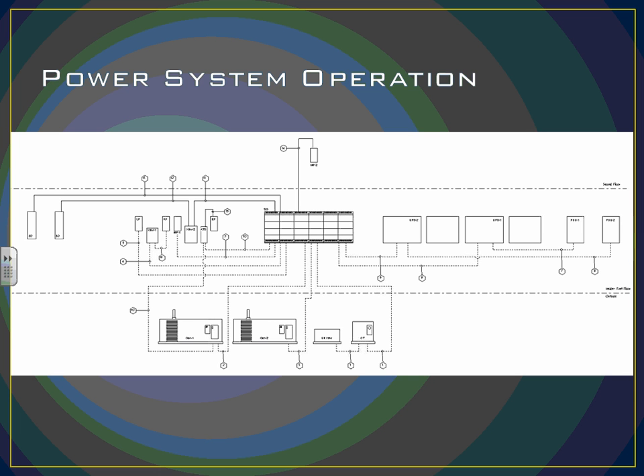These will be our bus duct for 208 and 480. 208 is fed from our secondary transformer right here, and the first transformer, which is our receptacle panel, which also runs the 208. And then we also had two mechanical panels, one for each floor, and our lighting panel as well, which runs 277/480. So for emergency power, upon shutdown, you're going to see the generators for closed transition start up, and then the ATS items will switch over for us. The generator one right here supplies power back to the ATS strictly for emergency power, for egress lighting and exit lighting, and then both of them supply the switchgear to supply 100% of the electrical load for the entire building.